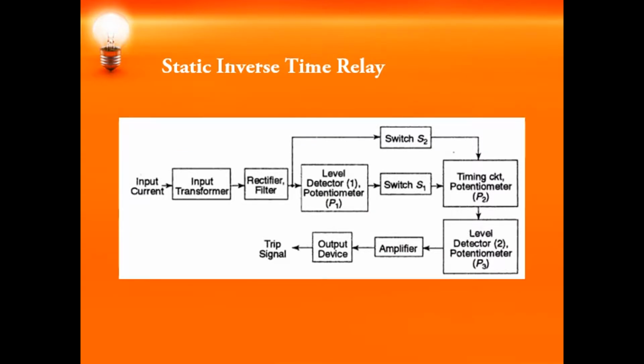Coming to inverse time static relay, the operating time of the inverse time overcurrent relay decreases with the increase in the fault current. It is inversely proportional, right? So for this, what we do is the charging of the capacitor takes place from a voltage which is proportional to the current which is flowing.